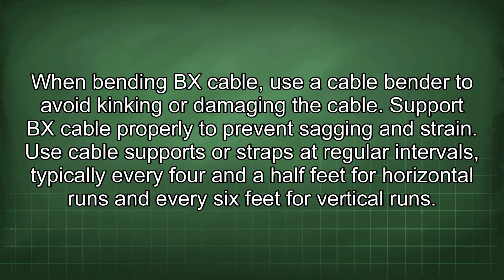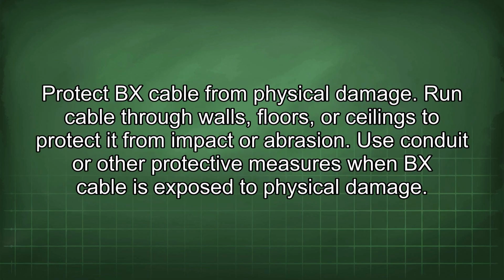Support BX cable properly to prevent sagging and strain. Use cable supports or straps at regular intervals, typically every 4.5 feet for horizontal runs and every 6 feet for vertical runs. Protect BX cable from physical damage. Run cable through walls, floors, or ceilings to protect it from impact or abrasion. Use conduit or other protective measures when BX cable is exposed to physical damage.